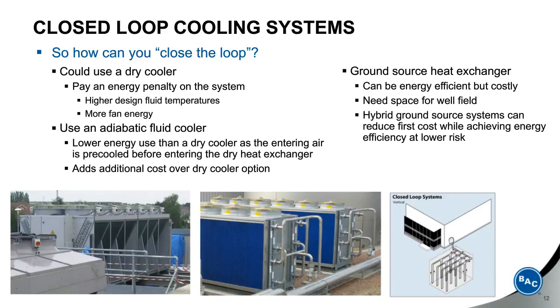You can also use a ground source heat exchanger, which can be very energy efficient but costly. And you also need space for the well field. You see a diagram of that on the right-hand side of the screen at the bottom. And what I found from my experience and research has been that hybrid ground source systems, which combine a well field plus a closed-circuit cooling tower or plate and frame heat exchanger and cooling tower can actually lower your first cost while you're achieving the same or better energy efficiency and at lower risk.